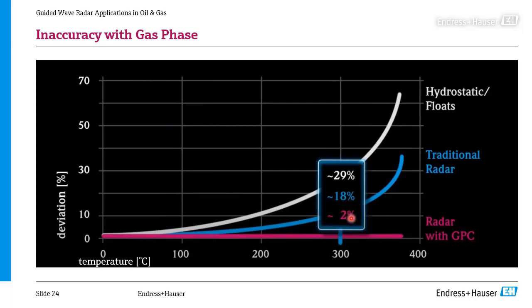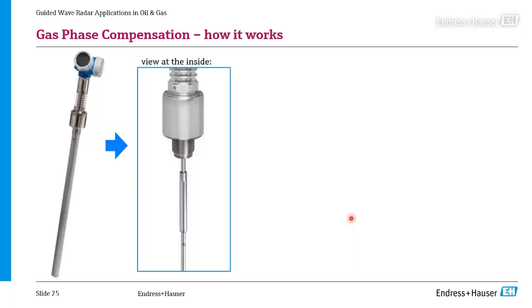You might ask, what is a GPC? I mentioned it before - it's a feature. If you order an Endress+Hauser Levelflex, our guided wave radar, with gas phase compensation, you get not just the standard rod - shown on the inside on the left-hand side of the guided wave radar - but a second rod as well, a reference rod. This, along with a lot of software algorithms, is the feature you directly see when you order a device with gas phase compensation.